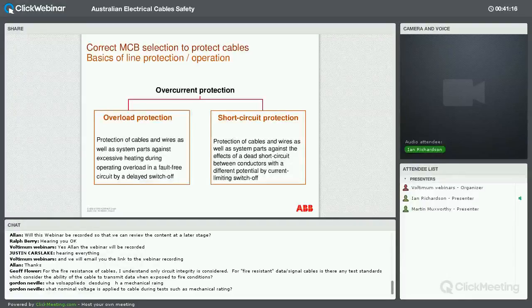When we get into slightly more intelligent devices, such as molded case breakers, they can have just a simple thermal magnetic trip, which is very similar in principle to a miniature breaker, but they can also have quite elaborate electronic trips, which gives us the ability to change the tripping curve in a number of ways.